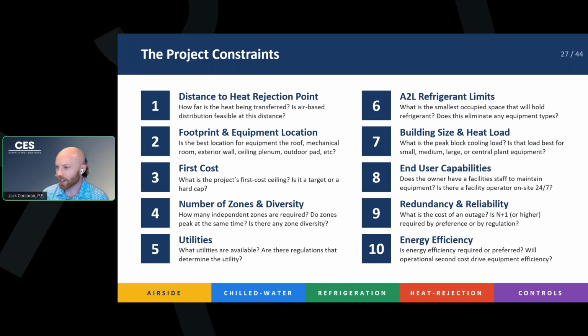And then these last three, right? Does the owner have someone on site to maintain it? These are pretty easy. You set it and forget it, which is awesome. You don't need to have an operator on site. Redundancy and reliability. These are like popcorn. You can just stick them all over the roof, and you can have a bunch of them add up to the total tonnage. And if one goes down, you still got all the other ones up there to handle the rest of the load. That's a pretty good one if it's one large zone. But if you have one unit serving one section of the floor and there's no backup unit, then there's no redundancy there. But for reliability, these rooftop units last 20 years, if not longer, if you maintain them correctly.